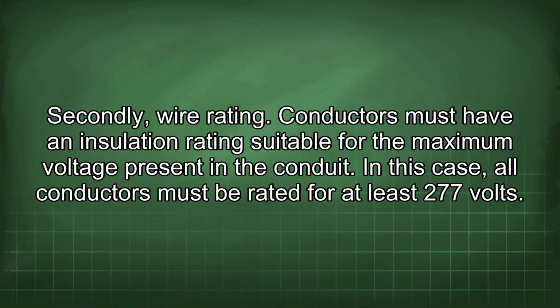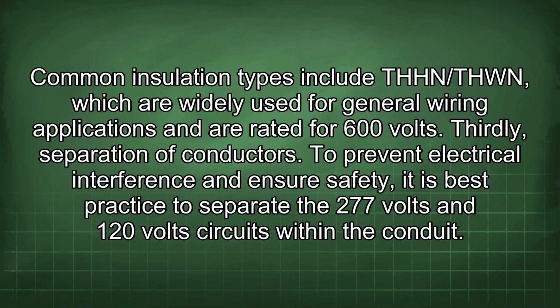Secondly, wire rating. Conductors must have an insulation rating suitable for the maximum voltage present in the conduit. In this case, all conductors must be rated for at least 277 volts. Common insulation types include THHN/THWN, which are widely used for general wiring applications and are rated for 600 volts.